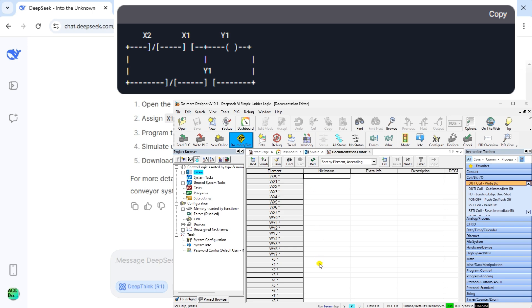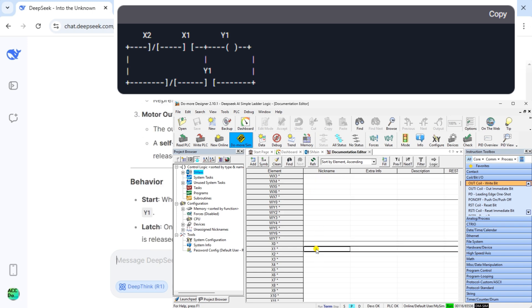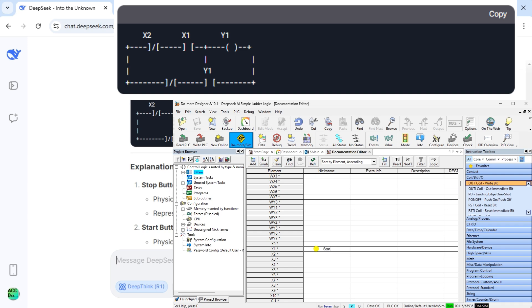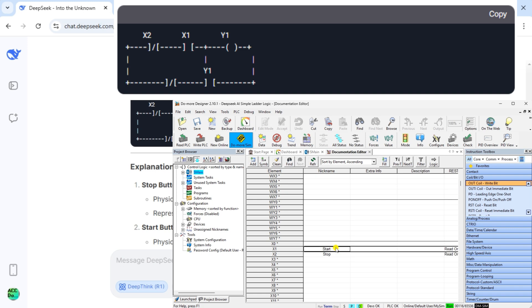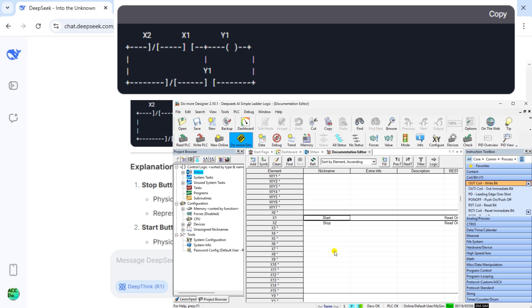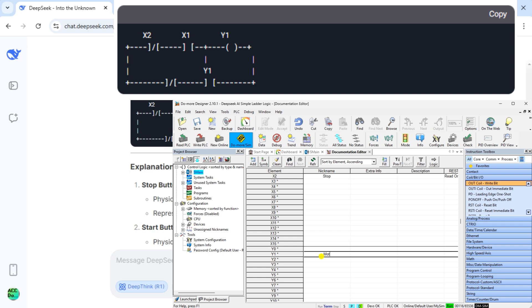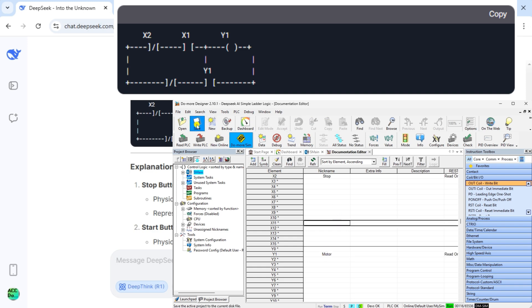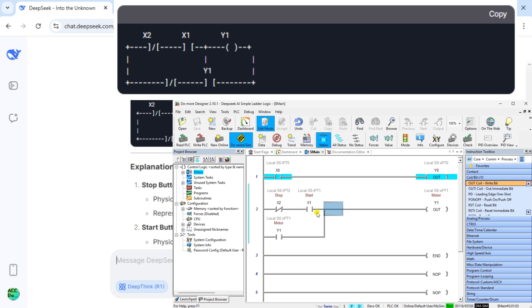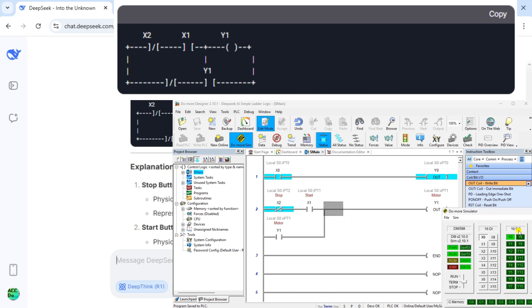Behavior: Starting — when X1 is pressed, current flows through X2 (closed) and X1 (closed), energizing Y1. Latch — once Y1 is energized, its parallel contact closes, maintaining the circuit even after X1 is released. Stop — when X2 is pressed, its NC contact opens, breaking the circuit and de-energizing Y1. Key notes: Safety — X2 is NC in hardware to ensure the motor stops if the circuit loses power or a wire breaks. Testing in DoMore Designer: open the software, assign X1 (start), X2 (stop), and Y1 (motor) in the I/O mapping, program the ladder rung, simulate using the built-in emulator to verify latch/unlatch behavior, then download to the PLC and test with physical buttons.